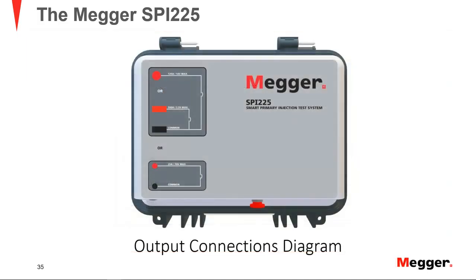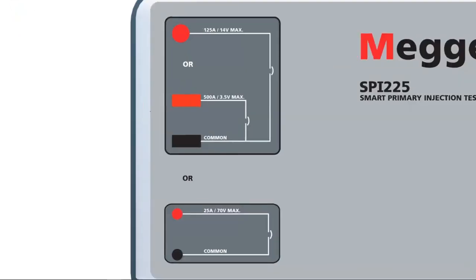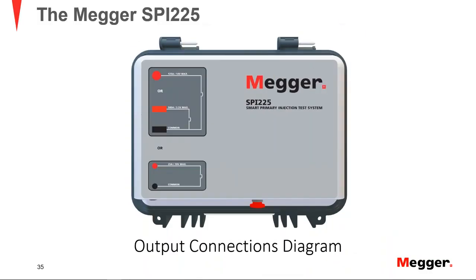Connections are summarized in the top overlay of the top panel of the unit. I will reiterate, it's really important that you only wire one tab at a time. So the front connection, you have your common and the 25 amp tab, and on the side you have one common and then your two tabs: 125, which is the round connector, and the 500 amps, which is the plate. Okay, so that's connections. Then we assume we're connected to the first pole on the breaker.